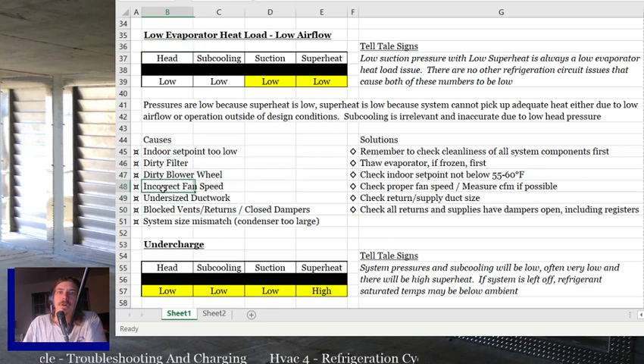So again, causes could be indoor set point too low, could be dirty filter, could be dirty blower wheel, could be the wrong fan speed. Always double check the fan speed. The guy behind you didn't necessarily do it right. All right, undersized ductwork.